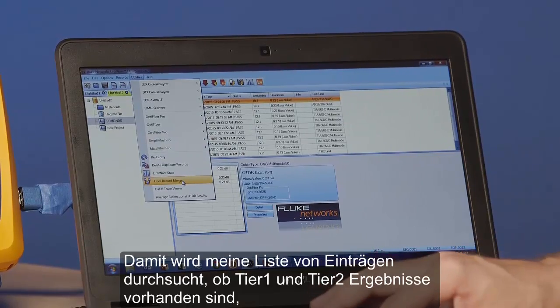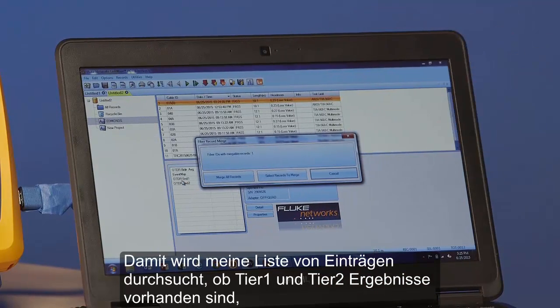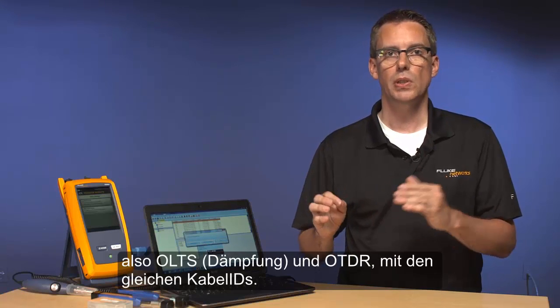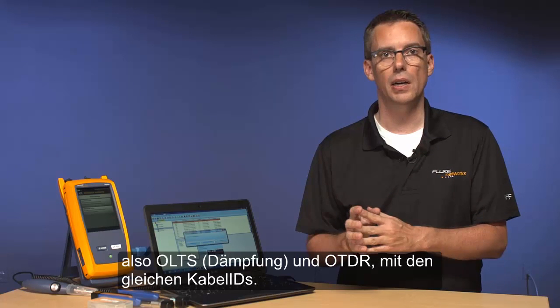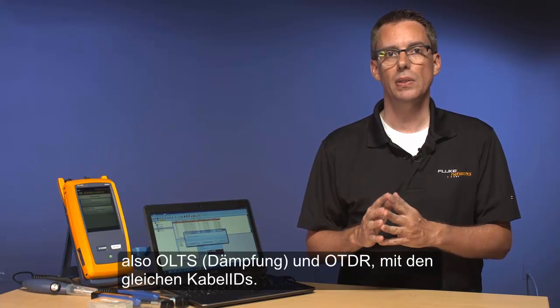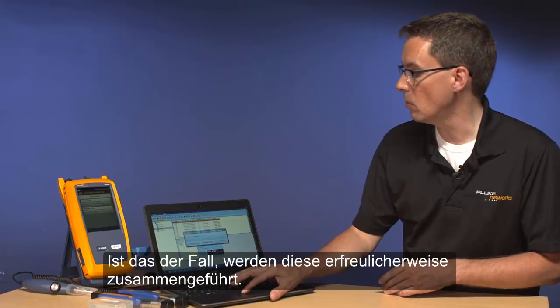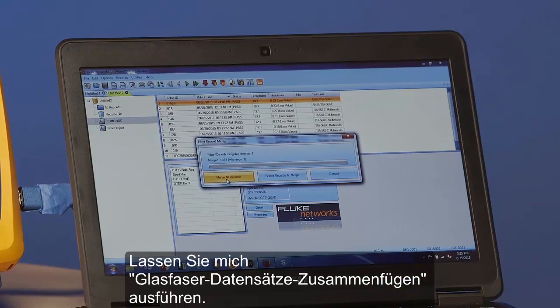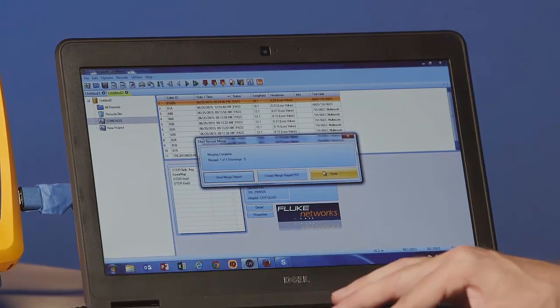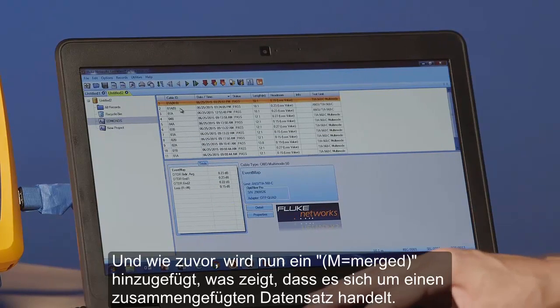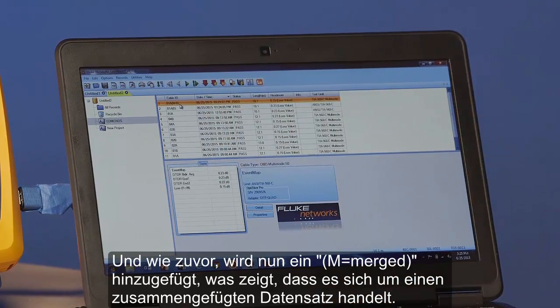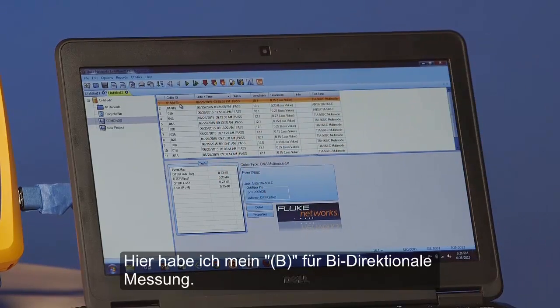What's going to happen here is it's going to look at my list of files and see if it can find a Tier 1 result and a Tier 2 result, that's an OLTS and an OTDR, with the same cable IDs, and if that is the case, then it will happily group them together. So let me do Merge All Records. And just as before, it appends it with M, indicating that this is a merged record, and I've got my B on there, indicating that this is a bidirectional test.